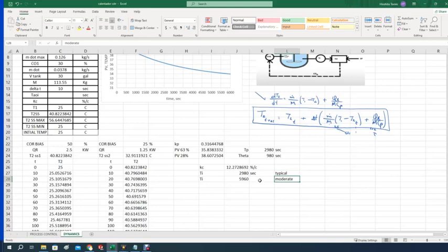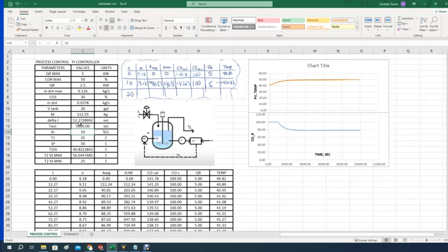Extremely important, what I'm going to say now. If I go to process control here, I want to eliminate tau I, the integral part. Make this number huge. What is a huge number? 1e6 is big, it's 1 million, and that will make the integral disappear. And when the integral disappears, you are using only proportional control, because that's basically what this boils down to, and you will not get to the set point that you want, the 50.